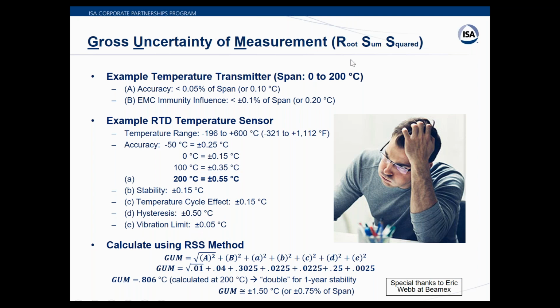So here's the trick. This is the RSS. So we've got all these numbers and we've converted everything to degrees C. So this is a statistical average. We're going to take each component of type B error and square it. So we're going to square the 0.1, the 0.2, and the 0.55. All these different numbers, we're going to square them, add them together, and then take the square root. So if you do all this math, you're going to end up with a combined uncertainty of 0.806 degrees. So we'll just say 0.8 degrees. And that's calculated at 200 degrees C. So it's obviously better at lower temperatures.